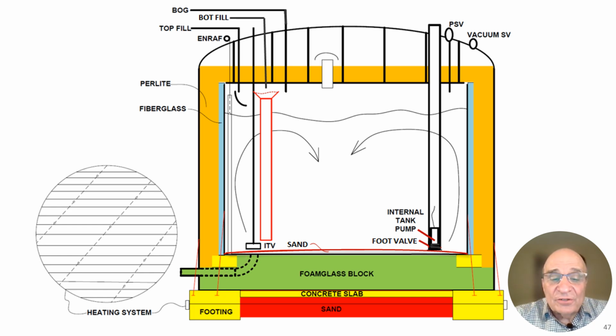Bottom penetrations are a concern only because if you get a leak in, let's say, this joint here, there's no way to shut off that LNG. You have to de-inventory the tank and then make that repair. However, if you have a newer tank that has a bottom penetration, they're equipped with internal tank valves, which allow you to shut the tank via this internal tank valve that's operated from the top of the tank. And it's operated, of course, either pneumatically or hydraulically from the top of the tank so that this valve can operate. And if you get an emergency shutdown, it would be typical for this valve to shut down depending upon the type of emergency shutdown.